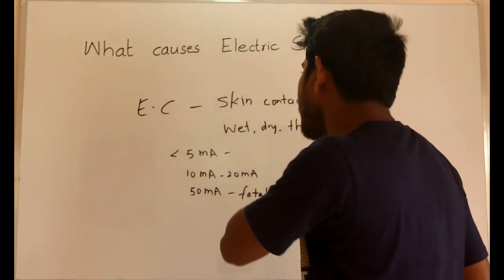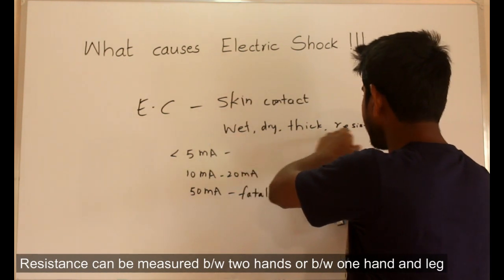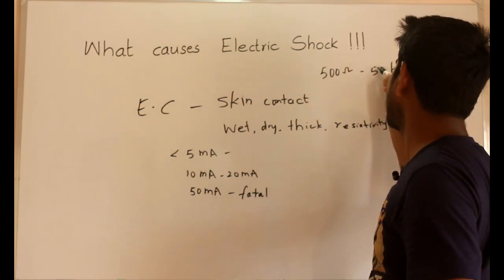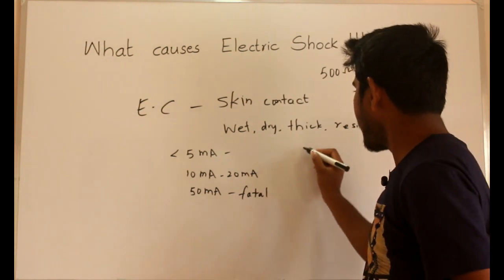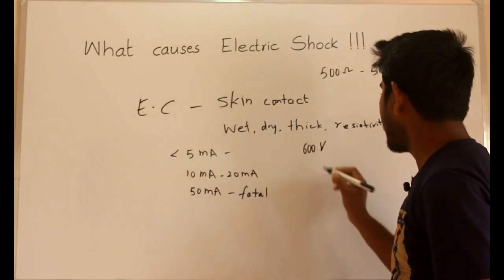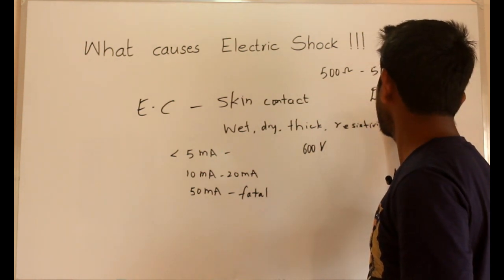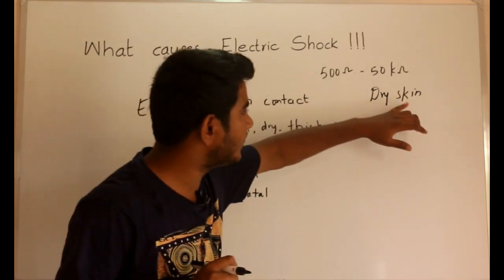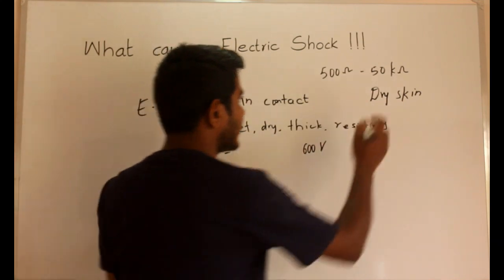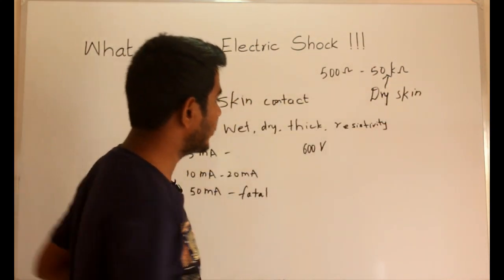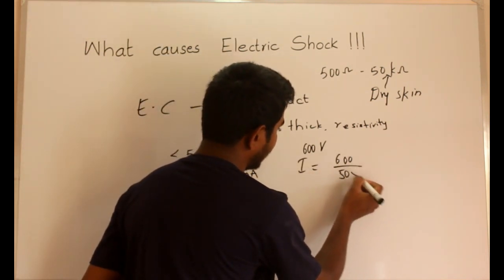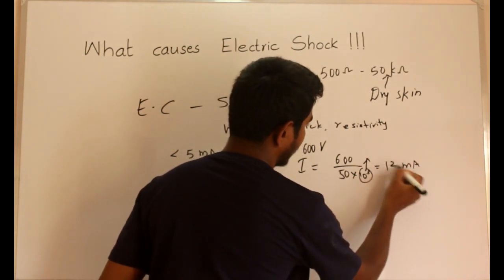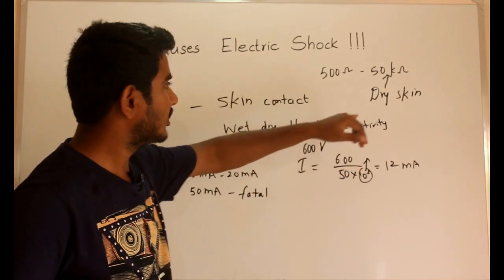The skin contact resistance, depending on wetness, dryness, thickness, and resistivity of the skin, varies between 500 ohms to 50 kilohms. Let us consider a 600 volt line, and let us consider dry skin. Dry skin will have more contact resistance than wet skin or a clammy hand. With dry skin, the resistance will be more, so let us consider the resistance is 50 kilohms. Then the current will be 600 volts divided by 50 kilohms.